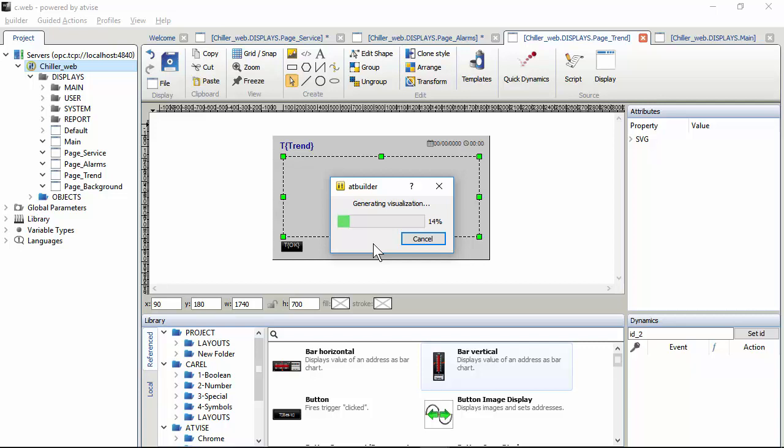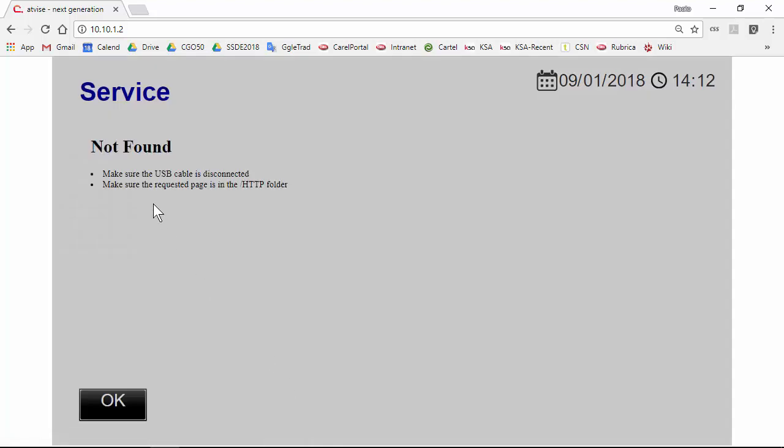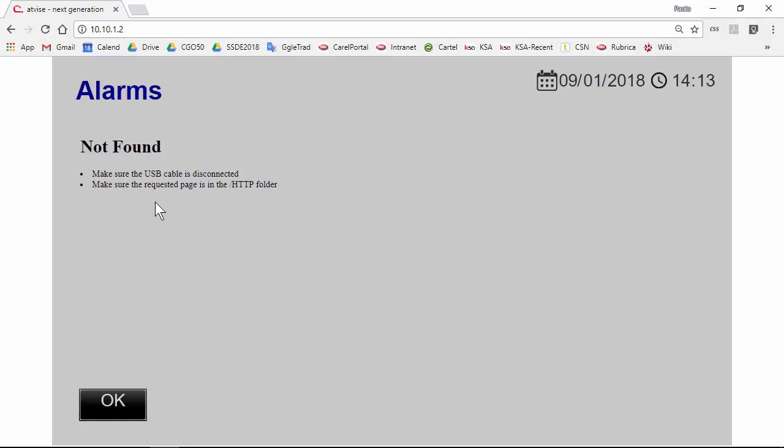I already know that it doesn't work, but I want to check. Reload, enter, and we don't see the web PGD here, nor the alarm list here and so on. What is the problem? First of all, we can read "not found, make sure that the USB cable is not connected." Why?